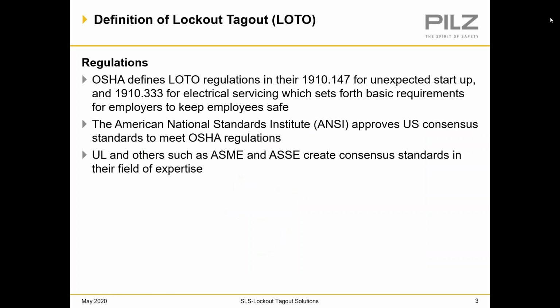These are the regulations for OSHA. The regulations for lockout are all with OSHA. OSHA defines lockout as 1910.147 for the unexpected startup of equipment, and 1910.333 for electrical servicing, which sets forth basic requirements for employers to keep employees safe. The American National Standards Institute, ANSI, approves U.S. consensus standards to meet the OSHA regulations, and UL and others also create consensus standards in their field of expertise.